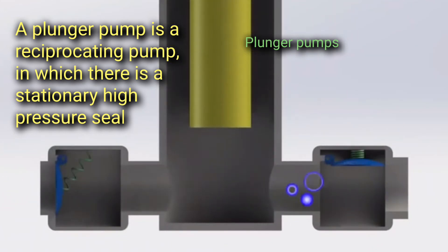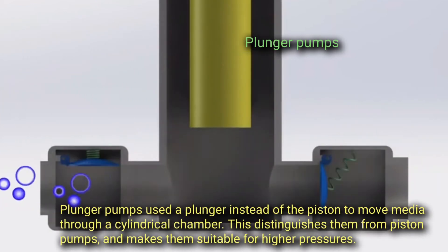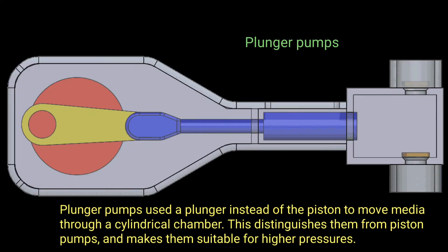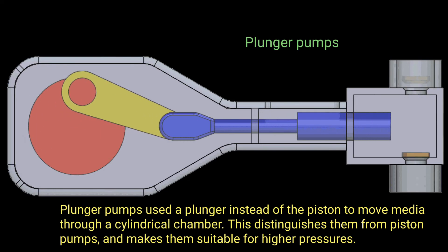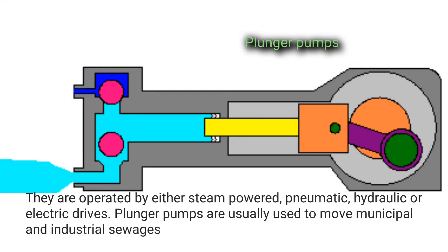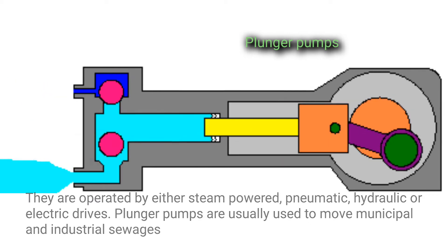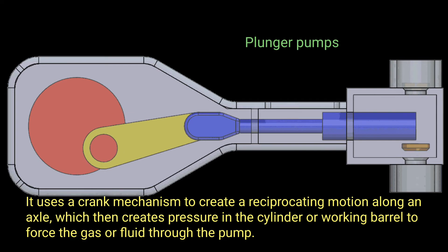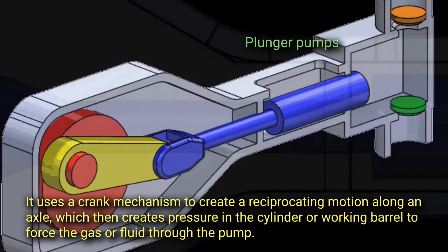A plunger pump is a reciprocating pump in which there is a stationary high-pressure seal and a smooth cylindrical plunger sliding through the seal. Plunger pumps use a plunger instead of a piston to move media through a cylindrical chamber. This distinguishes them from piston pumps and makes them suitable for higher pressures. They are operated by steam-powered, pneumatic, hydraulic, or electric drives. Plunger pumps are usually used to move municipal and industrial sewage, using a crank mechanism to create reciprocating motion along an axle to force fluid through the pump.